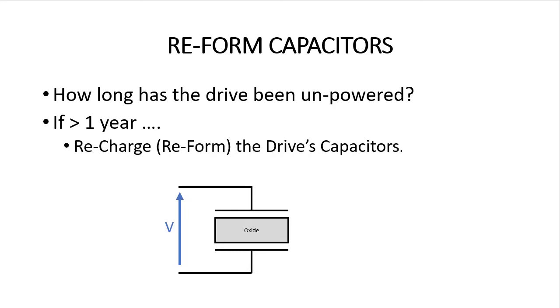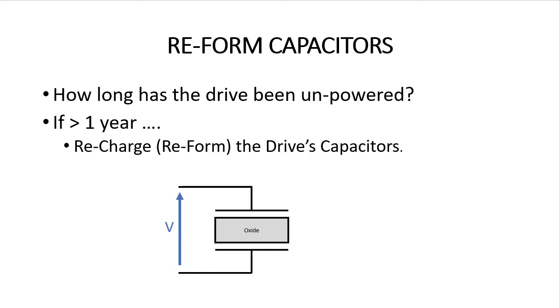and the huge resulting inrush current can damage the capacitors, which shortens the life of the drive and costs you money. So reforming the oxide layer before applying a load to the drive is really important.